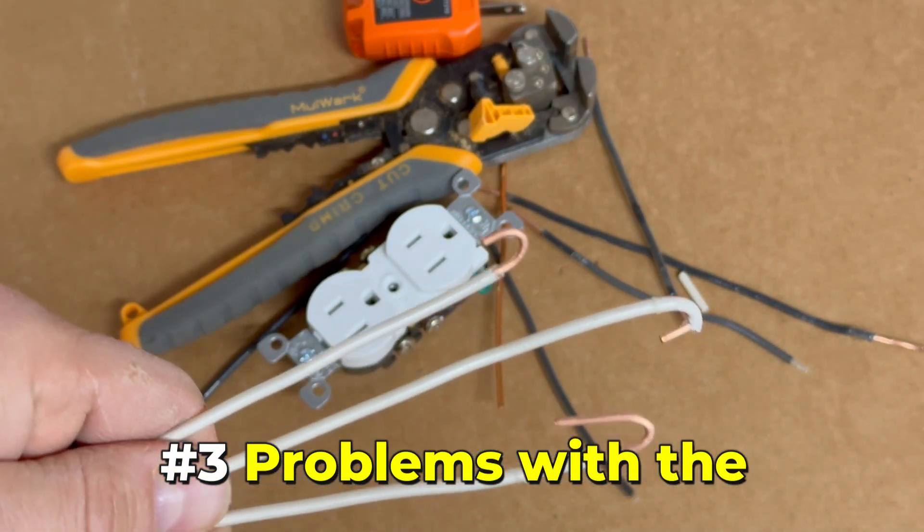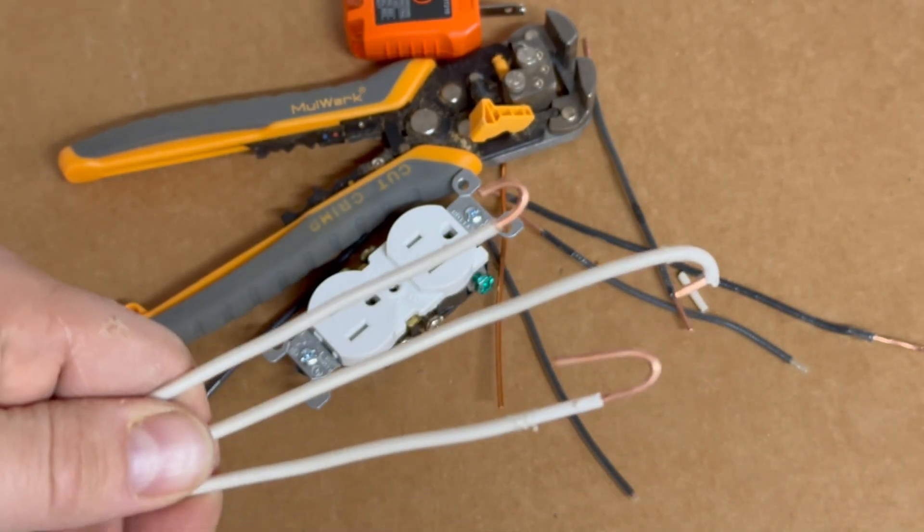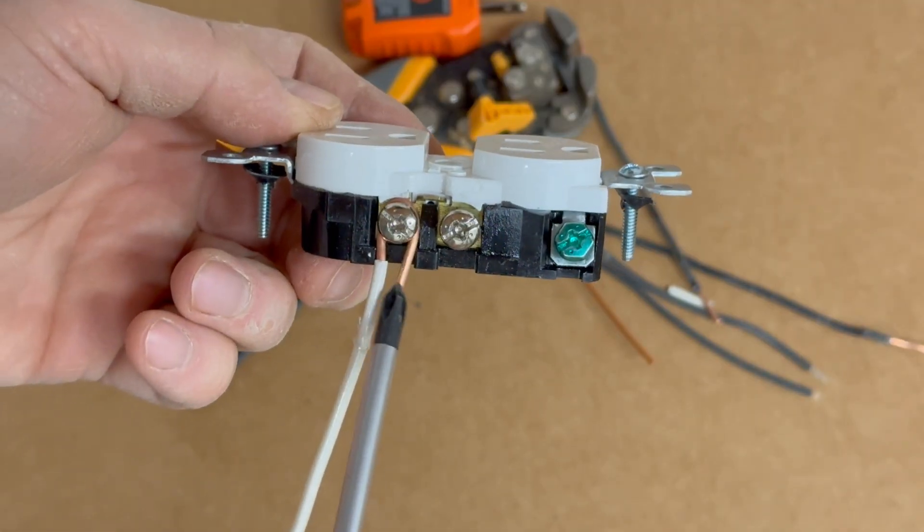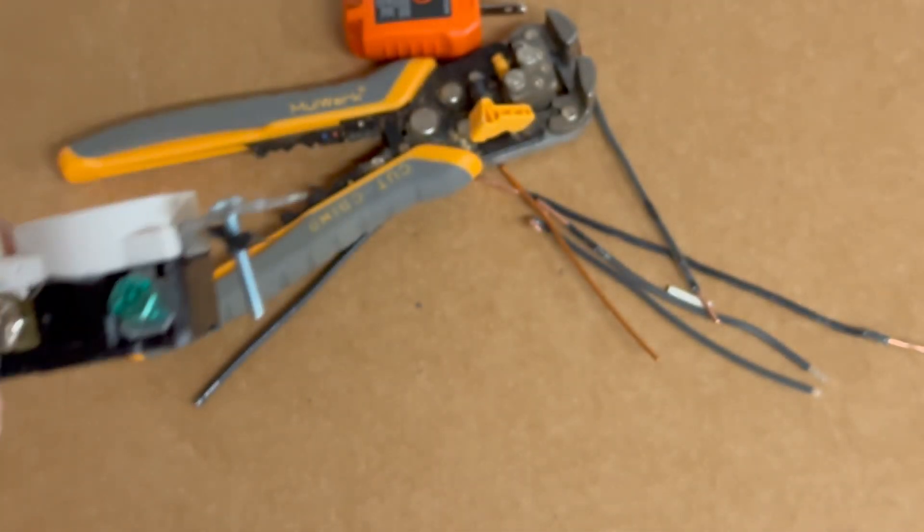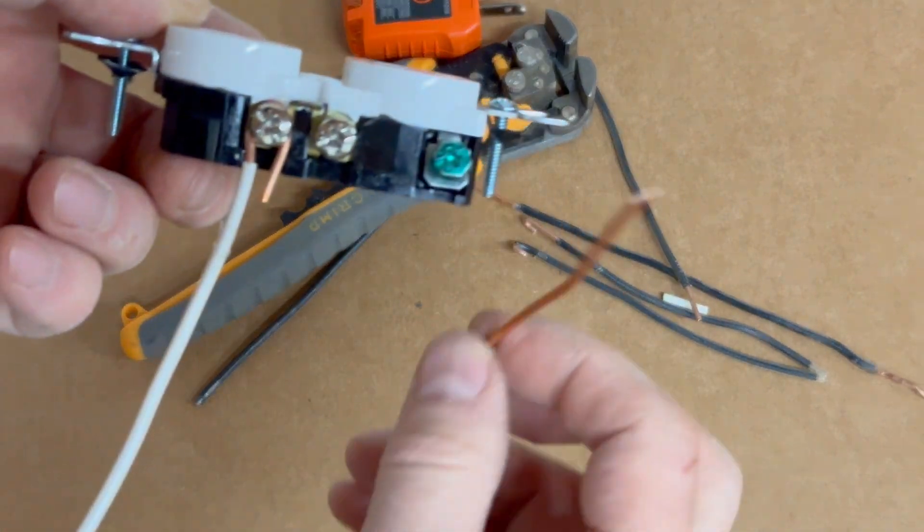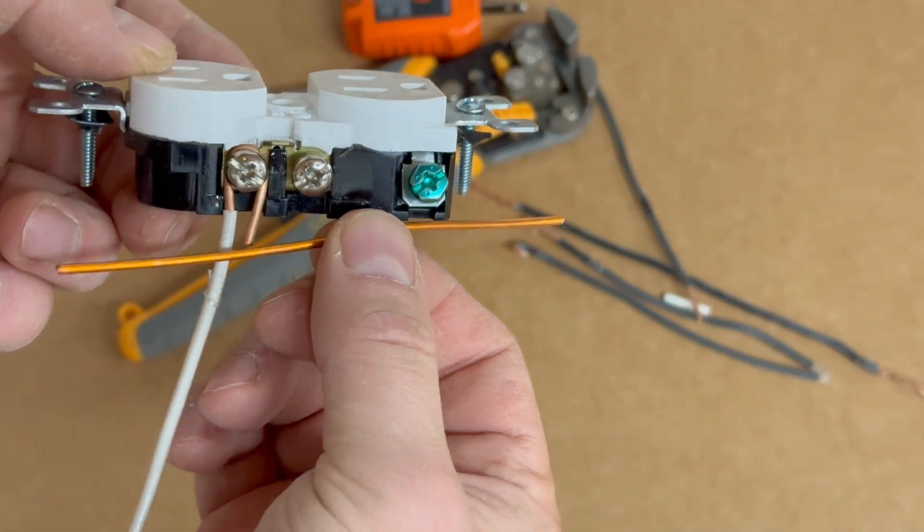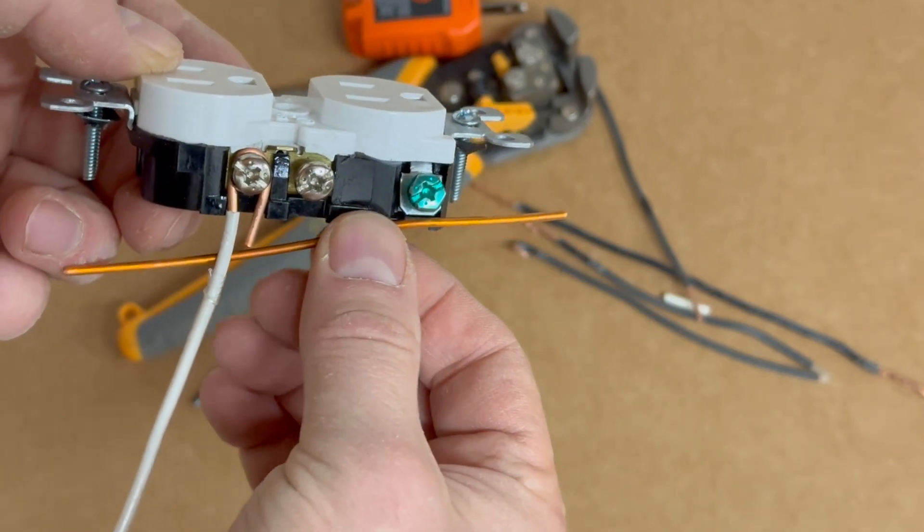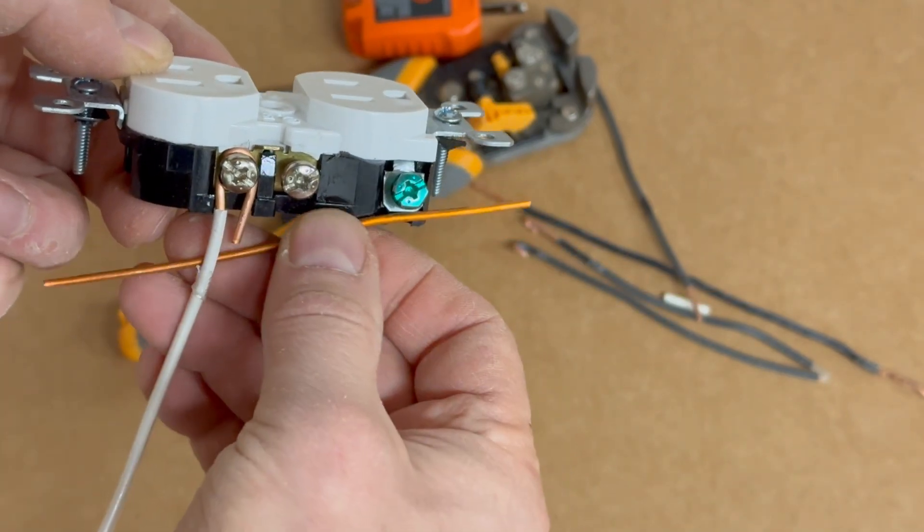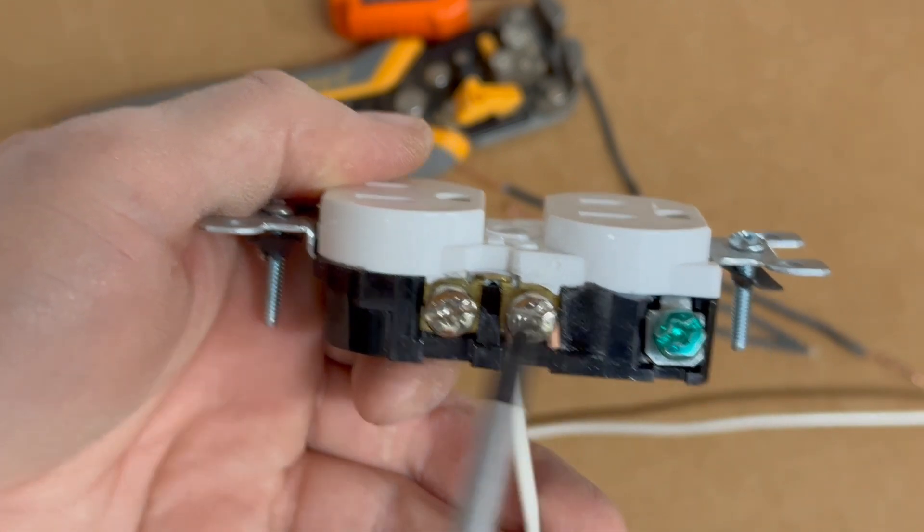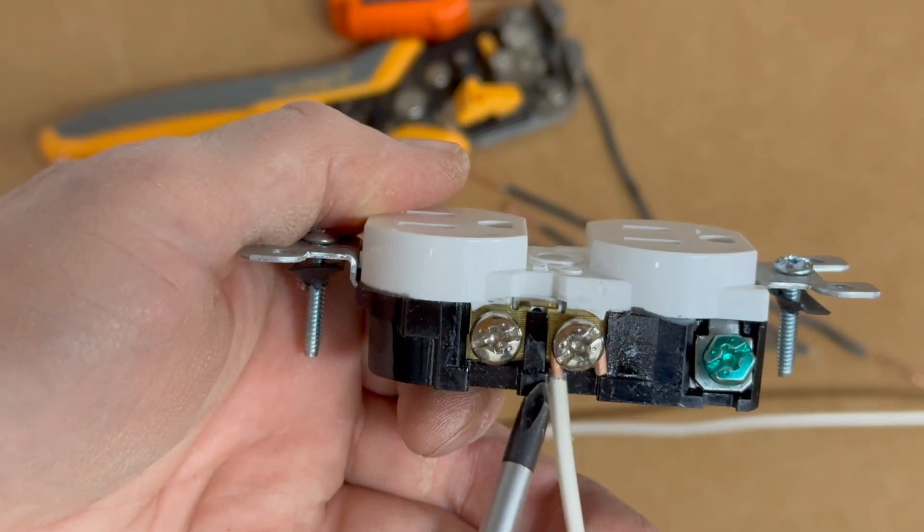Common wiring mistake number three: problems with the hook. If you strip too much wire, the excess will stick out past the outlet. While this might still work, it won't provide a proper connection and could potentially short out if it comes into contact with other components or with other wires. The correct amount of insulation to remove is three-quarters of an inch when making a hook.